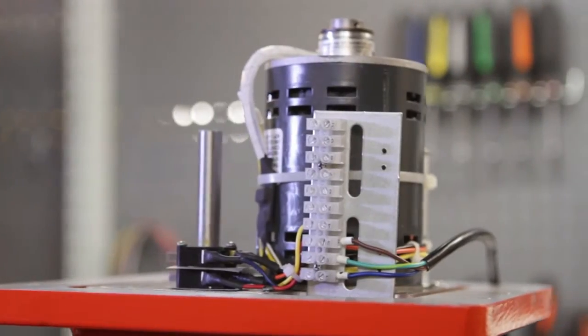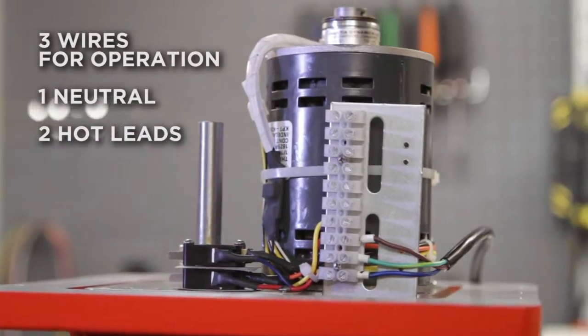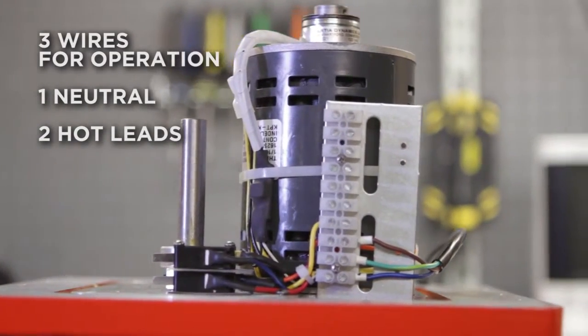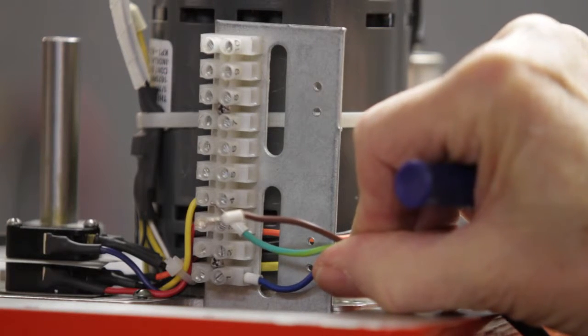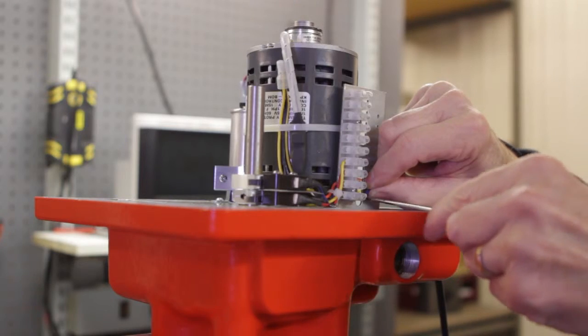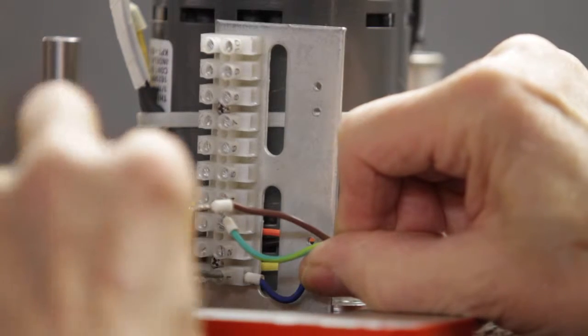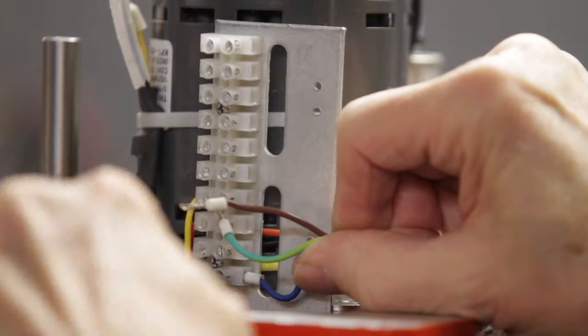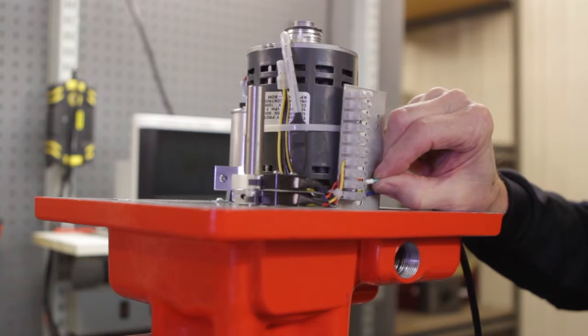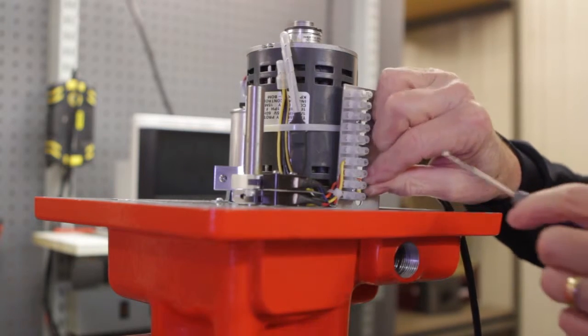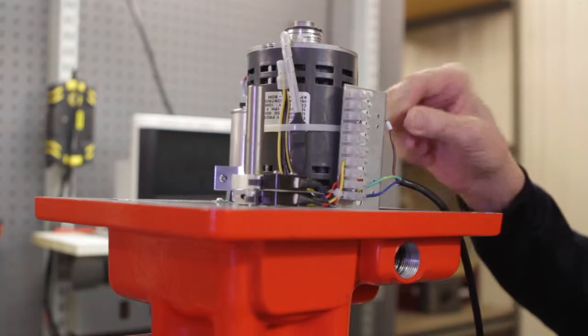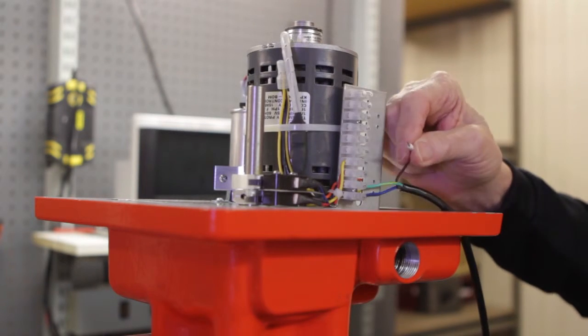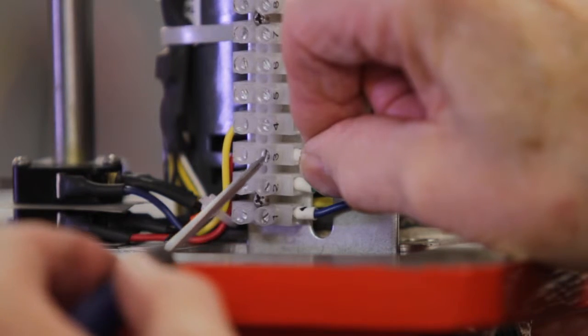A standard actuator requires three wires for operation: a neutral and two hot leads. A neutral is connected to terminal position number one. A hot lead to terminal position number two is used to open the actuator, and a hot lead connected to terminal position number three is used to close the actuator.